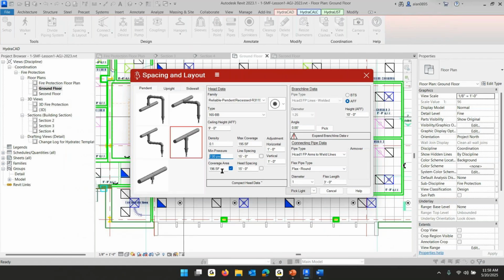usual minimum pressure. I'm going to say, I know I'm not going to go over 14 by 14. I could go to 15 by 15, but since I'm trying to fit into a ceiling tile, I'm just going to say plan on 14 by 14. You're allowed to put the heads as much as 15 feet apart, but these are constraints. They are not the answer.